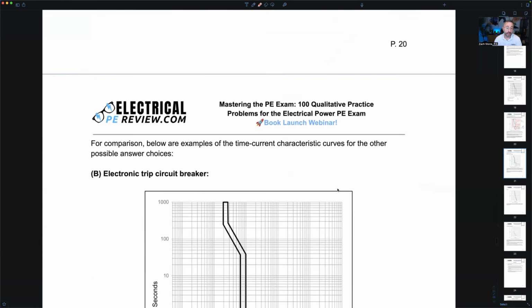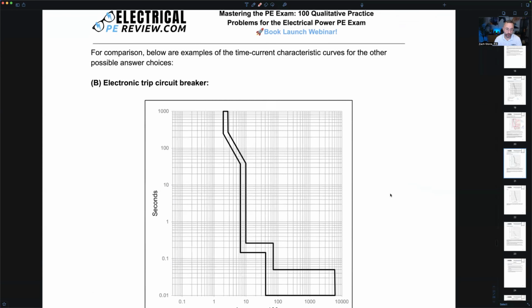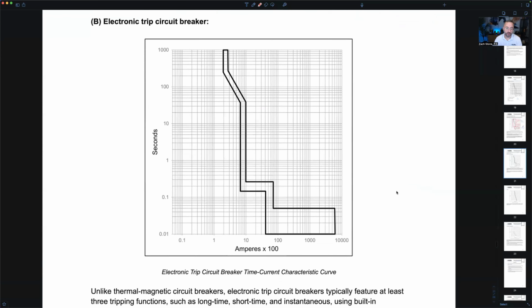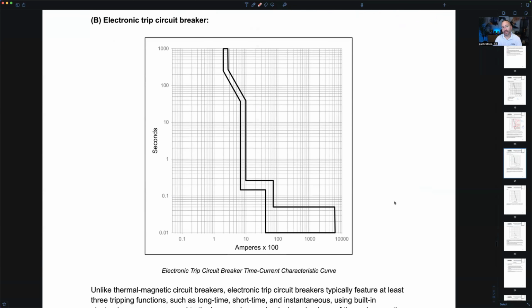All right, next one, electronic trip circuit breaker. First of all, what's the dead giveaway that this is not a thermal magnetic circuit breaker? What's the unique characteristic of a thermal magnetic circuit breaker? How many types of trip functions does it have? Which is the same number of trip regions on the time current characteristic curve that represents those trip functions. Yeah, thermal mag only has two. We have instantaneous trip, no time delay, and we have long time thermal trip.